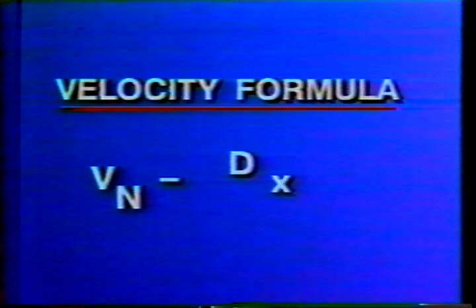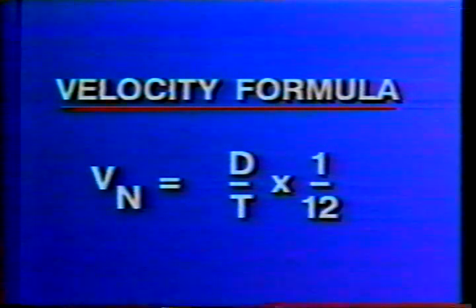Once the time and distance of the ultrasonic pulses have been measured, the velocity can be determined by using this mathematical formula, where Vn equals wave propagation velocity in feet per second, d equals path length in inches, and t equals transit time from the V-meter in seconds.